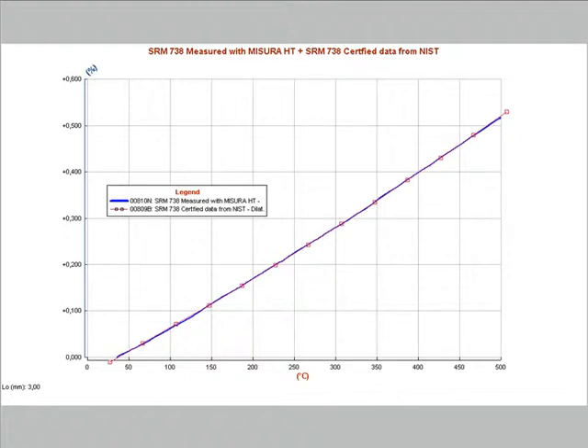In traditional dilatometers, the sample is contained inside the measuring system which itself expands with temperature. When the measuring system is made with alumina, the expansion of the measuring head may be much bigger than the expansion of the specimen itself. For this reason, it is absolutely necessary to apply a correction curve which accounts for the expansion of the measuring system.